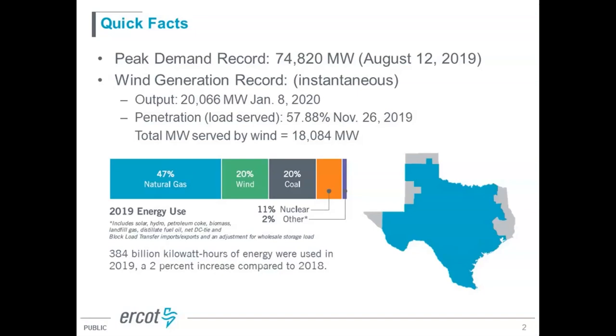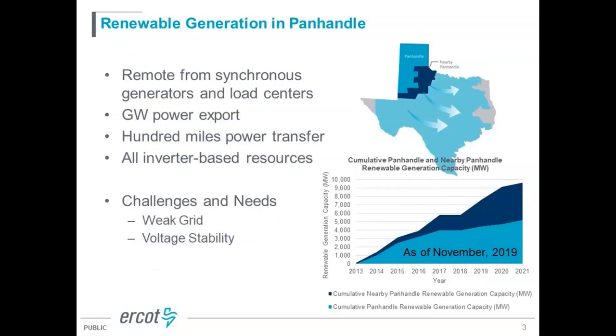And we do have a lot of renewable generation, especially wind generation, in ERCOT. The highest output from wind generation has exceeded 20 gigawatts. In terms of instantaneous penetration, we are already very close to 58%. This really drives a lot of the renewable integration and the needs of the system, including the synchronous condensers in the region.